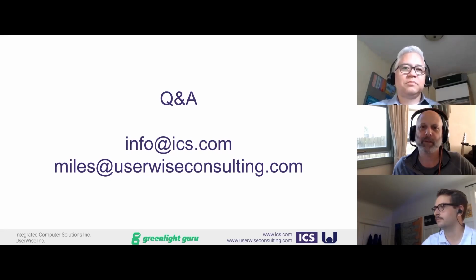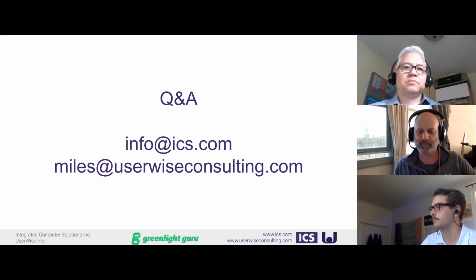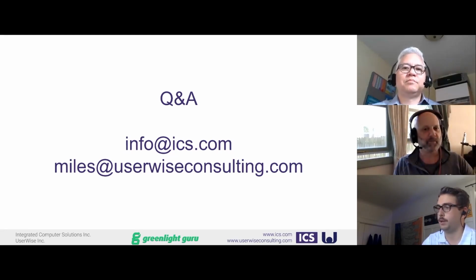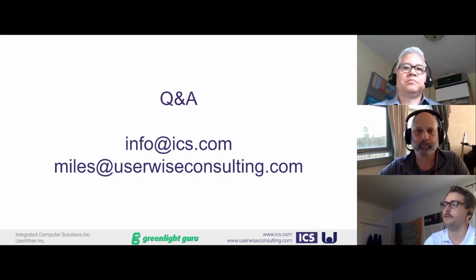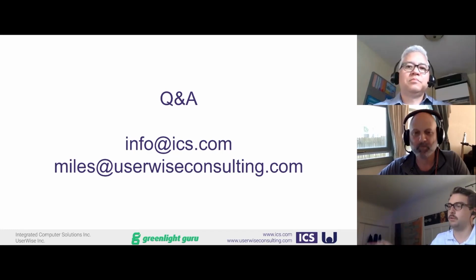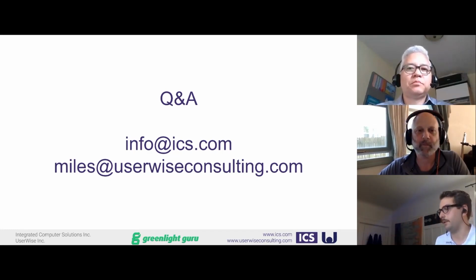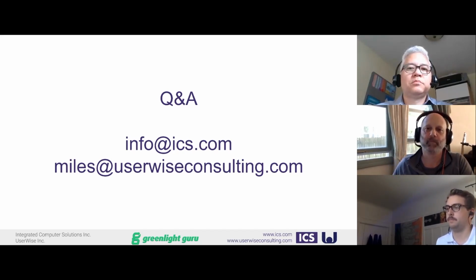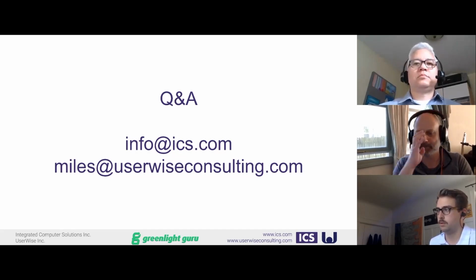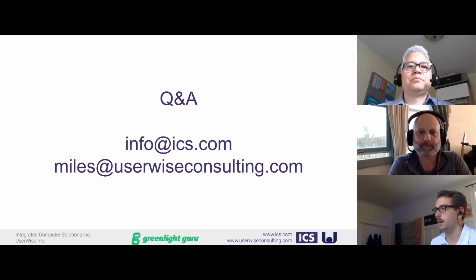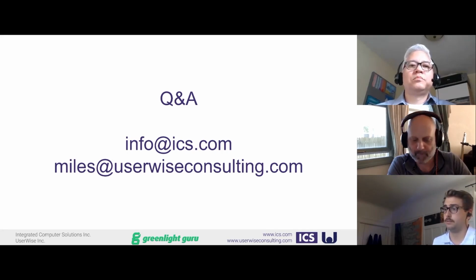So Navdeep asked a question: how to determine the sample size for usability testing? For validation testing, FDA is very clear, 15 minimum per user group. So if you have 3 different groups of users, lay users, surgical techs, or nurses who are going to be using this product, you're going to need 45 participants at the minimum. In terms of formative testing, we generally shoot for around 6 people minimum per user group, but it's not a statistically significant sample size for formative testing. I believe 15 is a statistically significant sample size for the FDA, but we're not looking at the rate of success based on each task during the actual validation test.